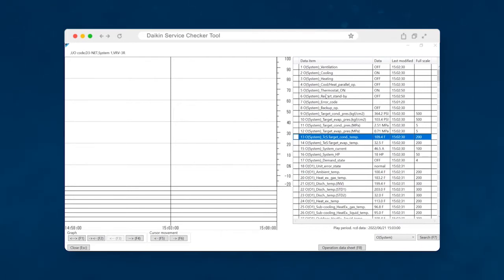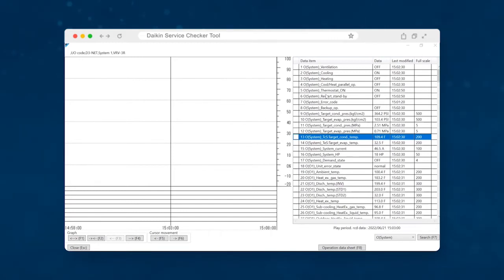So a system that's running low on charge can result in damaged compressors, shortened compressor life. The first thing that you will want to look at is what mode is the unit operating in? I like to get a baseline for each one of the modes. You have three modes. You have cooling, which means that all of the indoor units are in cooling. You have heating, which means that all of the indoor units are in the heating mode, and then you have parallel mode, which means that you have a mix of some being in cooling, some being in heating.